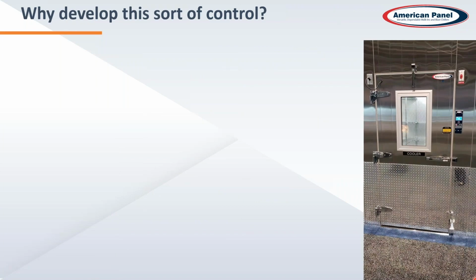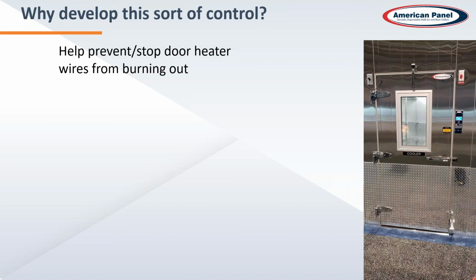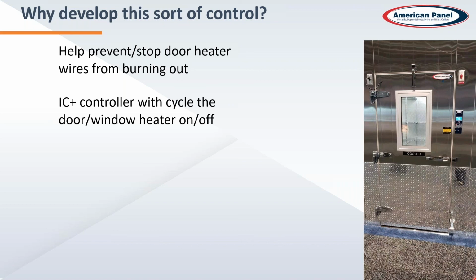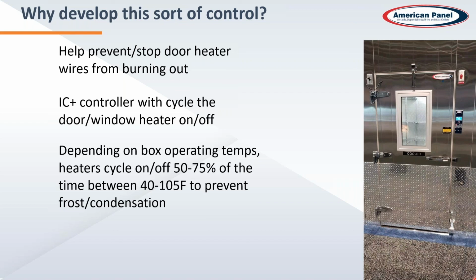So why have we developed this sort of control? Well, it started a number of years back. Our first main goal was we wanted to help prevent or stop door heater wires from burning out. Typically, a heater wire would either be run 100% or maybe run on a rheostat. But what we do with the system IC Plus controller is we will actually cycle the door heater wire and, if equipped with a window, the window heater on and off. And depending on the box operating temperatures, the heaters will cycle on and off between 50 and 75% of the time when the temperature is showing between 40 and 105 degrees. And what this does is it will prevent condensation or frosting around the perimeter of the door. And this is all coolers and freezers, heater wire equipped for both from American Panel.